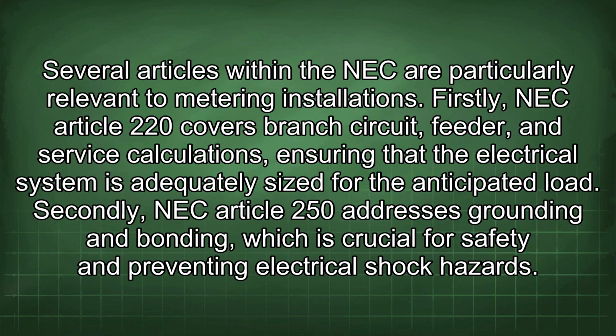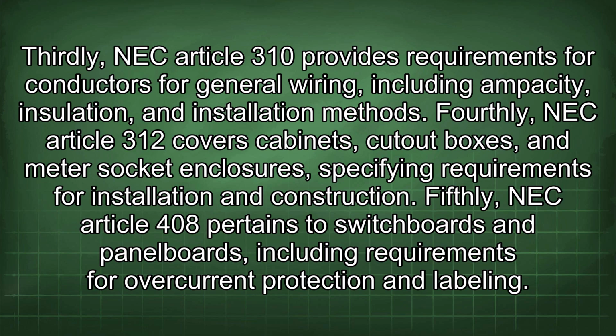Several articles within the NEC are particularly relevant to metering installations. Firstly, NEC Article 220 covers branch circuit, feeder, and service calculations, ensuring that the electrical system is adequately sized for the anticipated load. Secondly, NEC Article 250 addresses grounding and bonding, which is crucial for safety and preventing electrical shock hazards. Thirdly, NEC Article 310 provides requirements for conductors for general wiring, including ampacity, insulation, and installation methods.